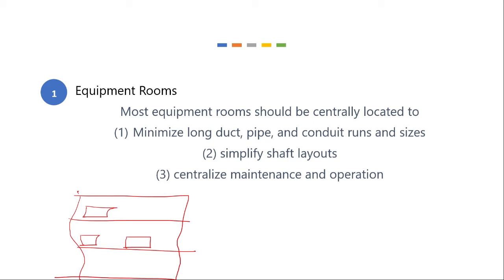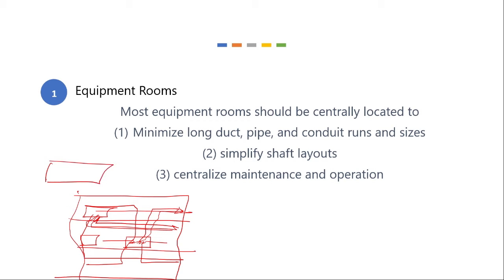if we put it up on the 3rd floor in the corner, we need to run some ducts all the way across and all the way down. Whereas if we put the HVAC room here in the middle of the building, we don't have to run our ducts very far. It's much easier. Every duct is shorter. And the thing is that air starts to cool as it travels. So sending air a long distance is very inefficient. So a long duct is inefficient, and as a result, to get the same effect, we have to make our duct wider.